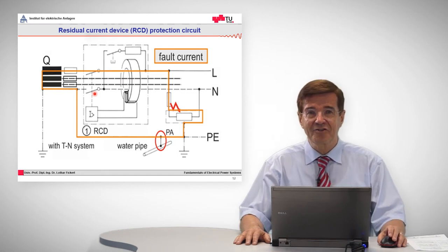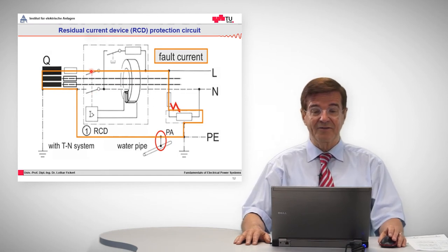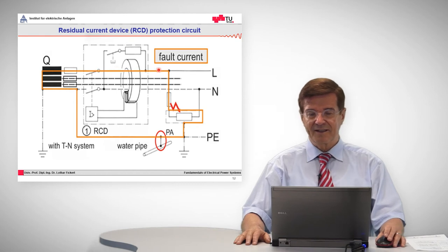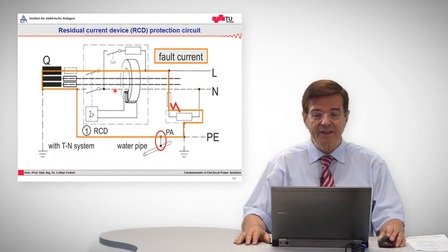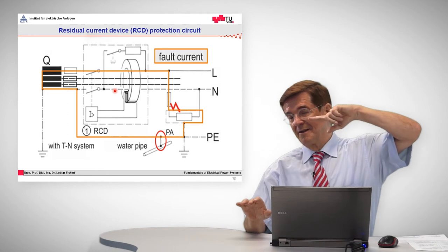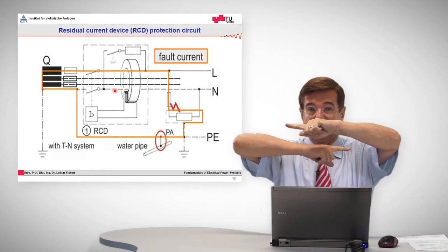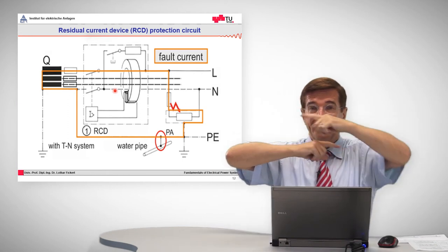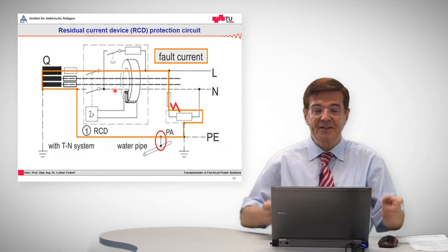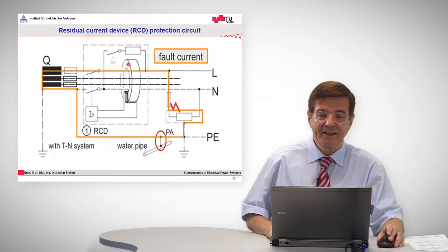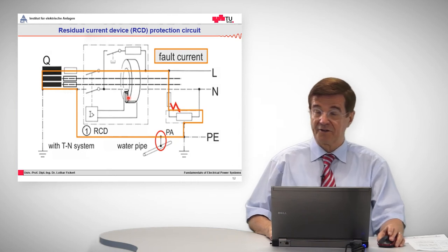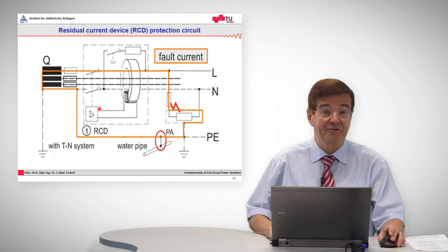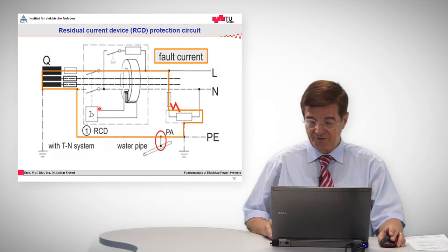By the way, the question is why doesn't it trip under normal circumstances? That's easy to understand. The current goes in here, goes regularly through our body, our lamp, whatever it is, and returns here. So we have one current going this way, one current going the other way, and they induce fields that are vice versa. The fields annihilate each other, so there is no field here. If there are no fields, there is no induced voltage. When there is no induced voltage, this will not trip.